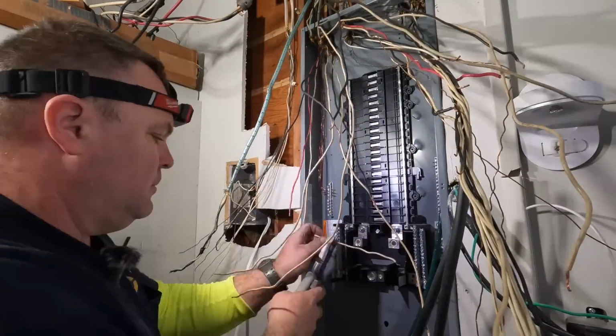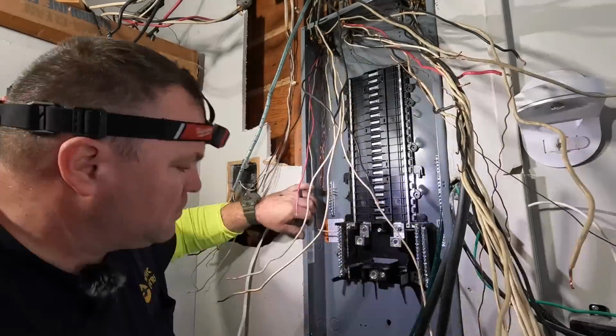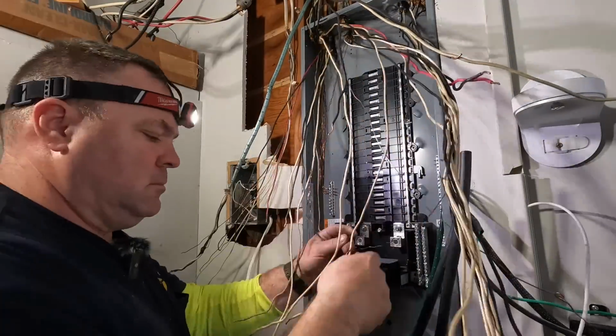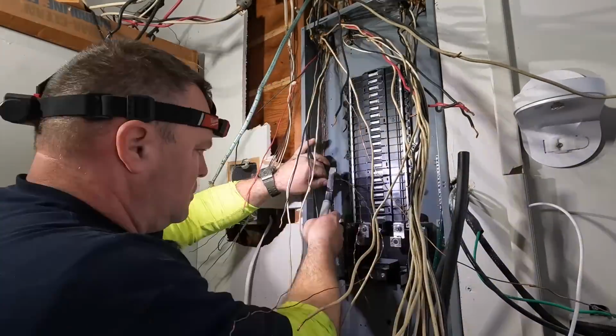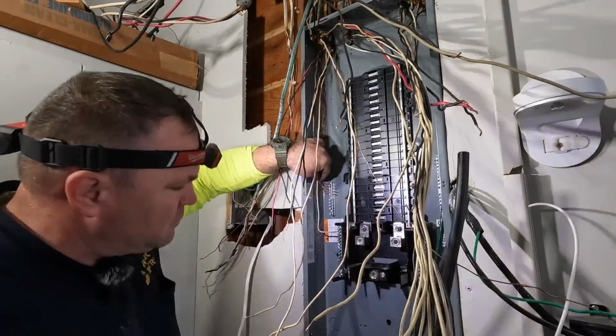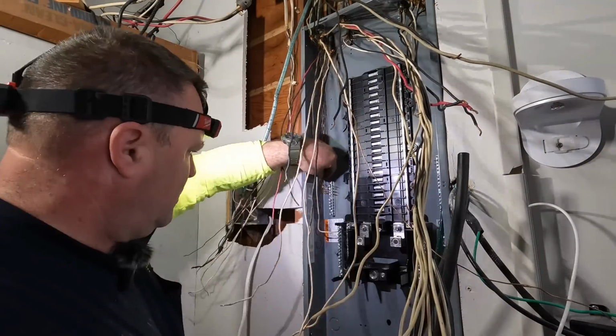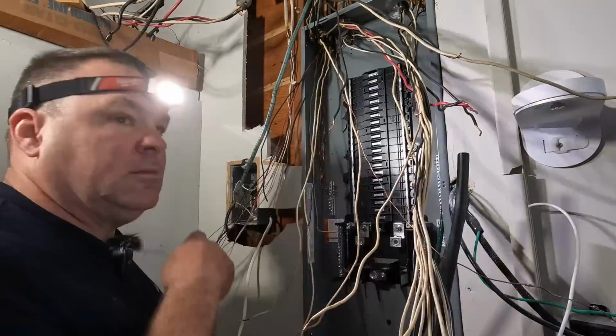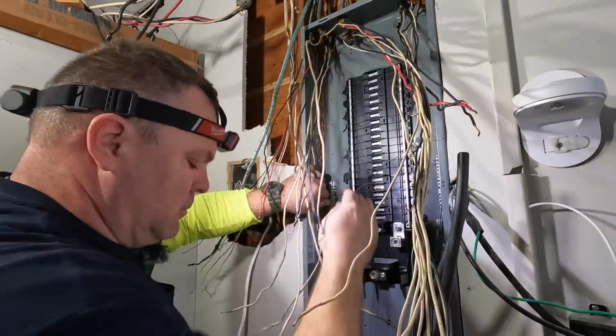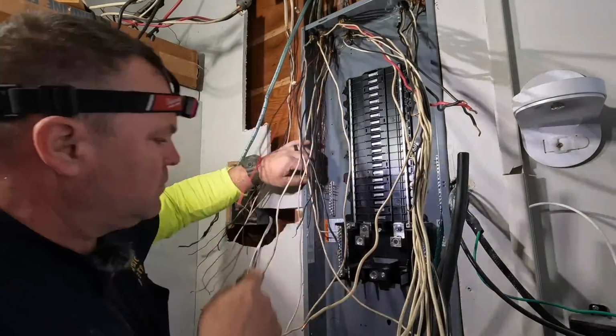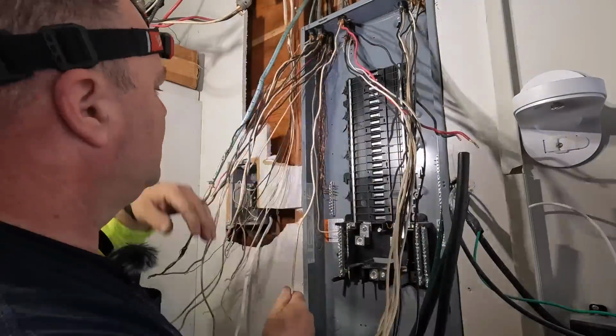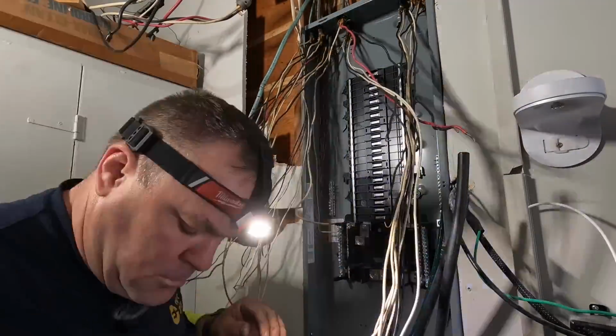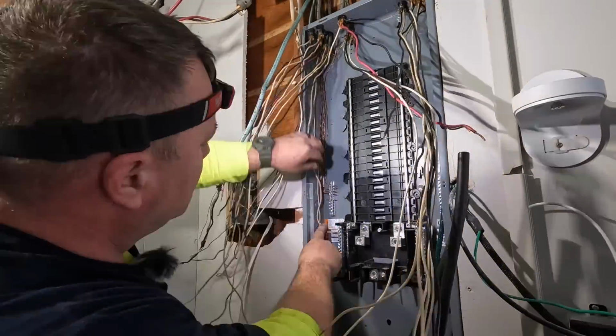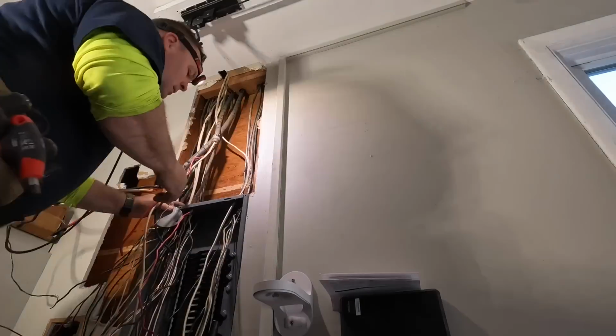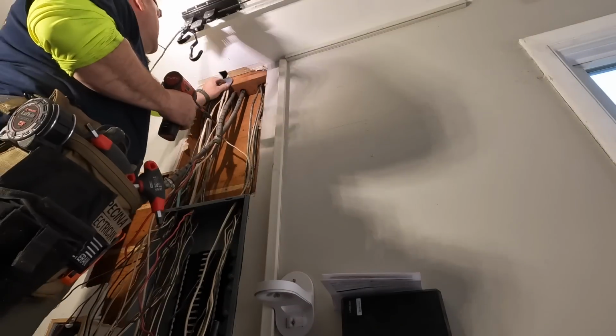They're not required here in New Jersey when upgrading an existing electrical service, but we did add a couple new circuits, and those would be required to have arc fault protection, GFCI protection, or both, if required by the National Electric Code. Article 210.8 shows the requirements for new circuits needing GFCI protection, and Article 210.12 covers the requirements for arc fault protection.